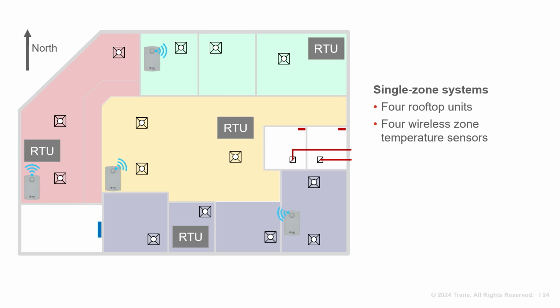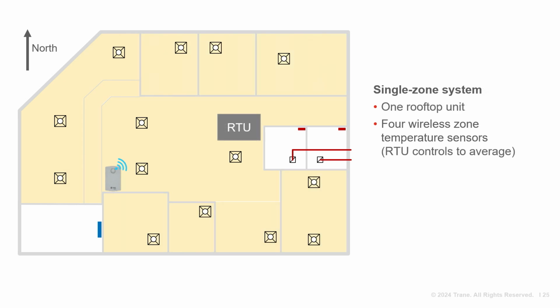To overcome this challenge, the design team might choose to install multiple smaller rooftop units, each with its own zone sensor. Here, we're showing 4 thermal zones with 4 different rooftops, each equipped with a zone sensor. This would provide more zones of control, but increases the installed cost, as well as the number of building penetrations and utility connections. Another option is to install multiple zone sensors and let the unit controller average the temperatures. The rooftop unit controller averages the readings to determine the required control action. So, a single zone system would treat the entire branch bank as a single thermal zone.